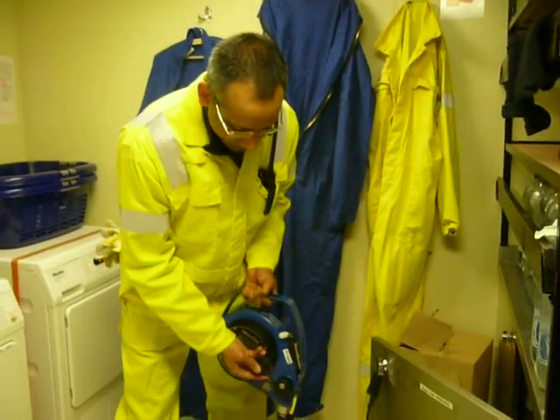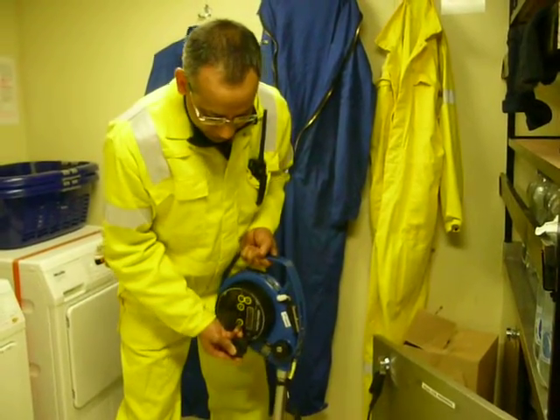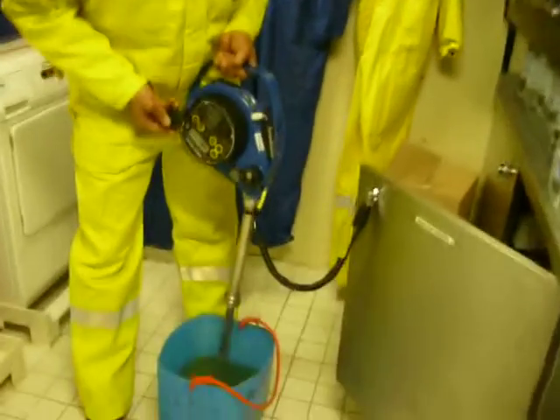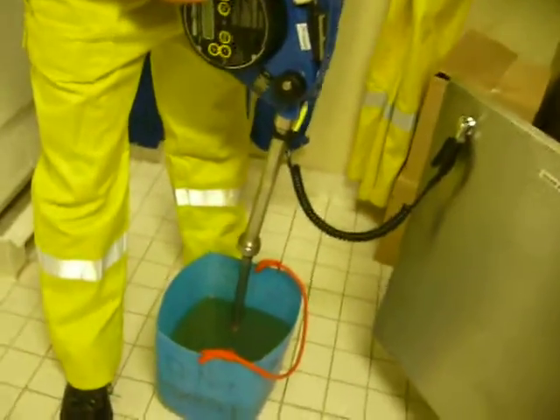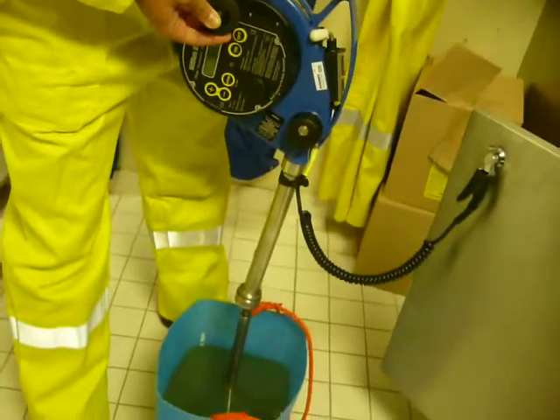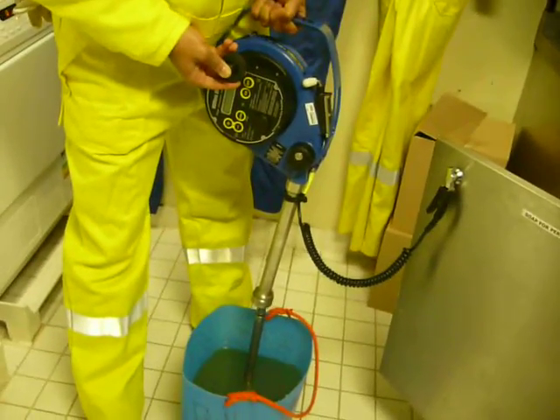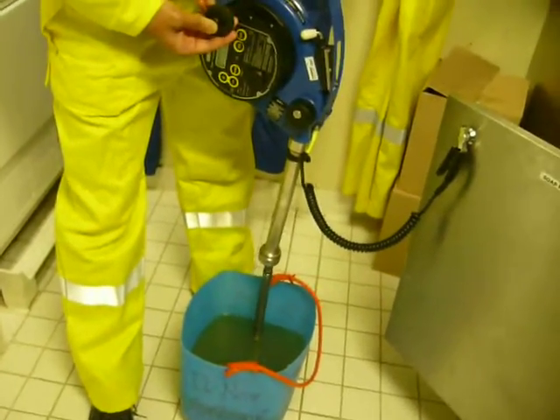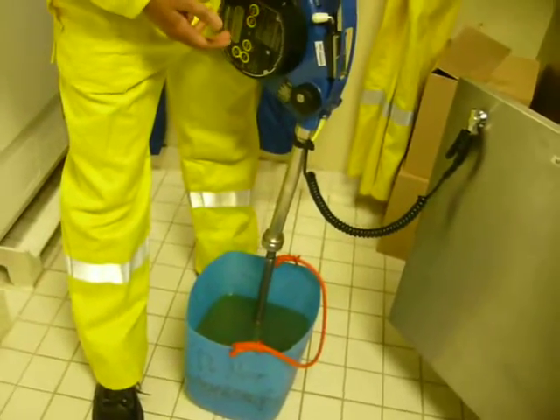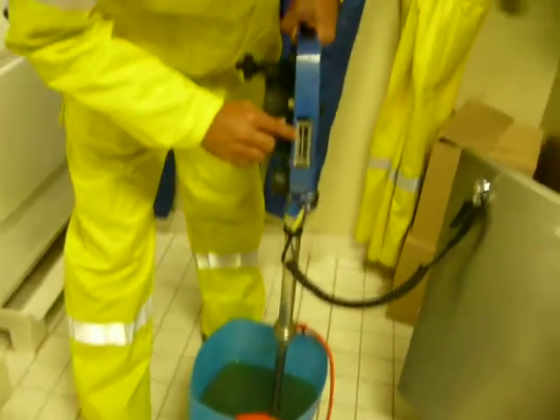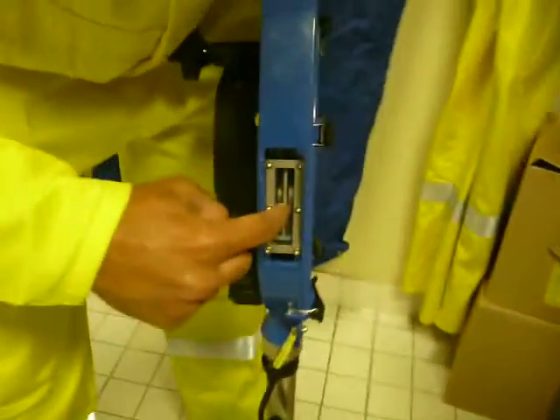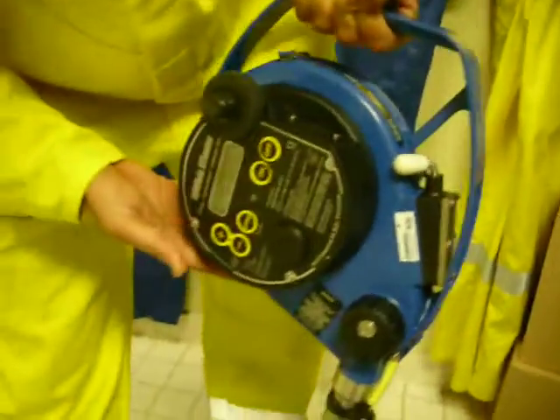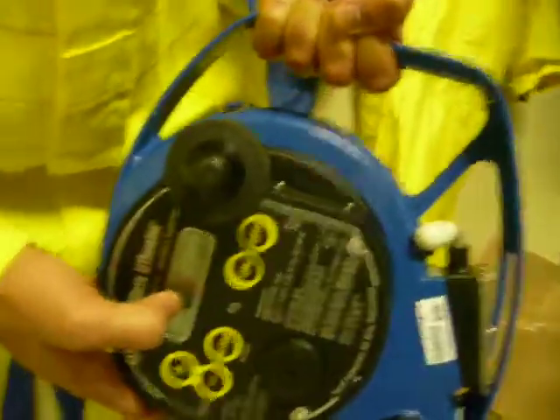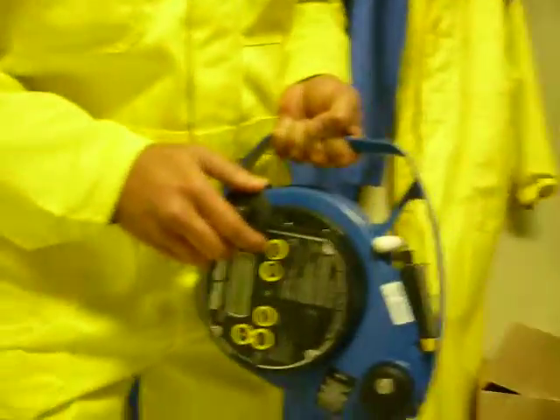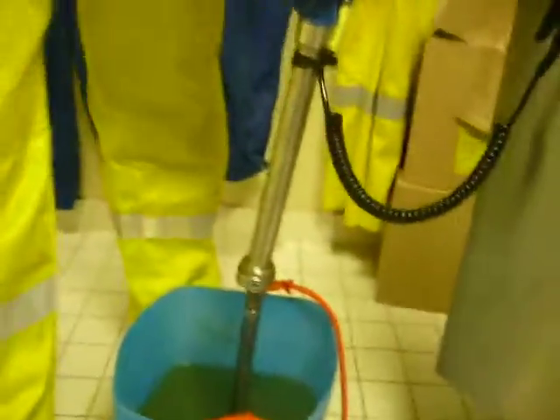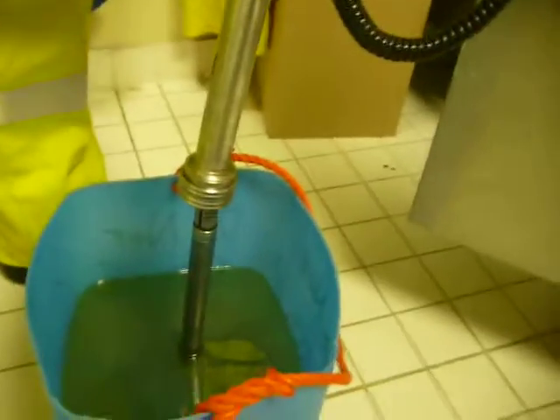So we'll start lowering the probe, and you can see it go down, and the sound will change. This is the level of the hydrocarbon in the tank, and here you can read out the ullage from this gauge, and it will also give you the reading here. The moment it goes down into the water, the sound changes.